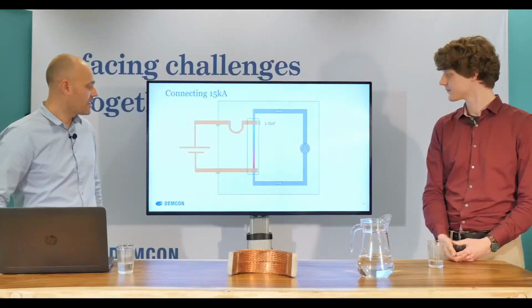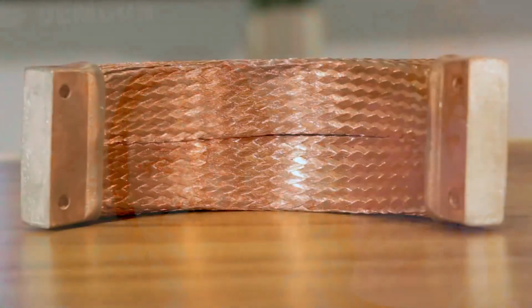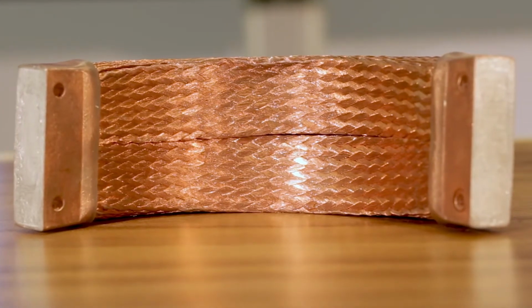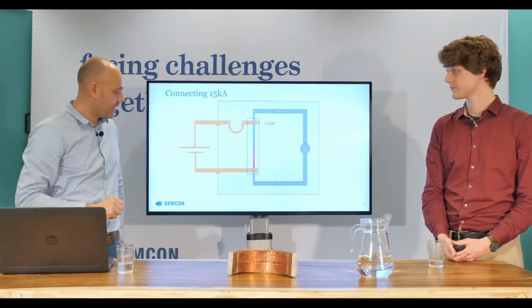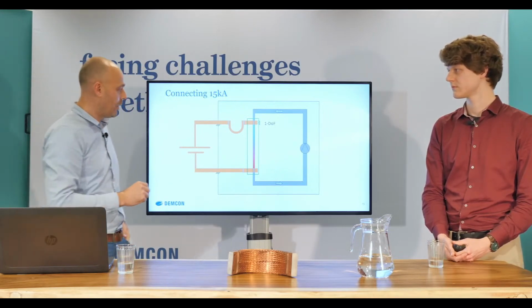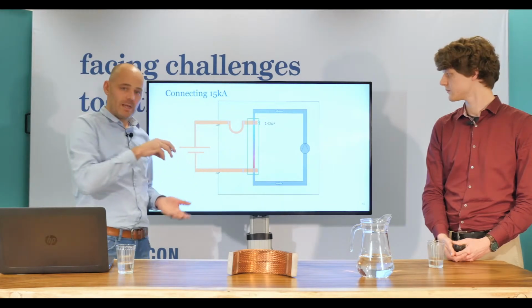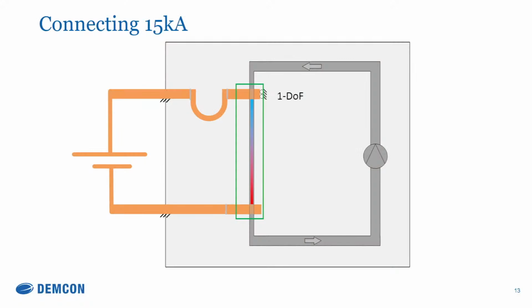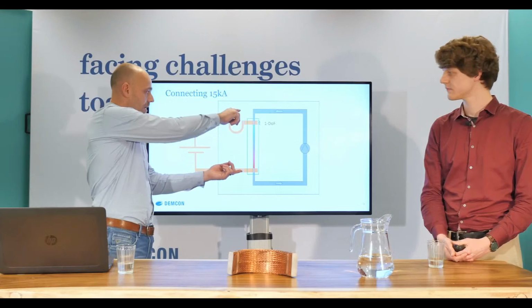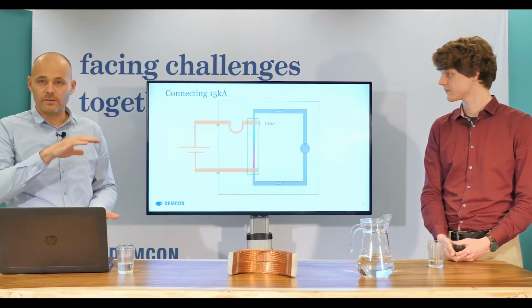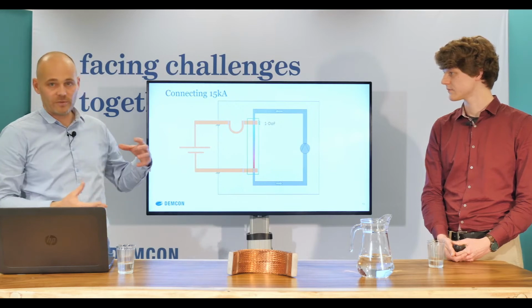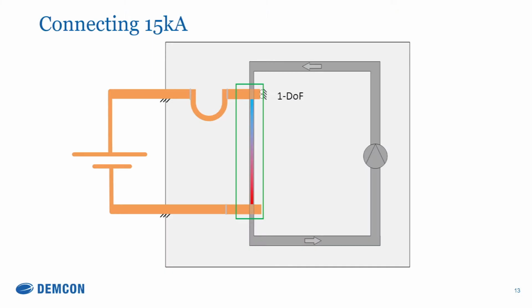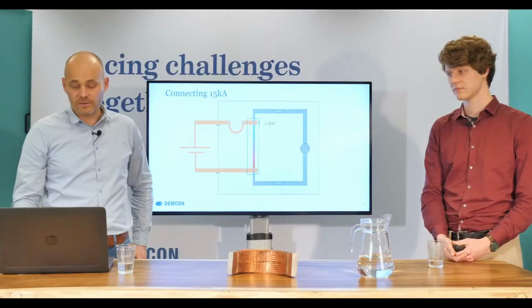Further to the test section itself, so we've talked about the U-bend shape here, the braided copper. Now we also need to talk about the expansion of the actual tube, the component. So this will expand and needs to be able to expand freely, because we only wanted to see the results of the stresses caused by the thermal gradient of the actual heat, and not the expansion of the tube. So again, this will be free in 1 degree. All other degrees need to be fixed, because there's a lot of weight on top of the top electrode, and we want to keep that from ruining our test, and ruining our tube. I'll go in a bit further on that.